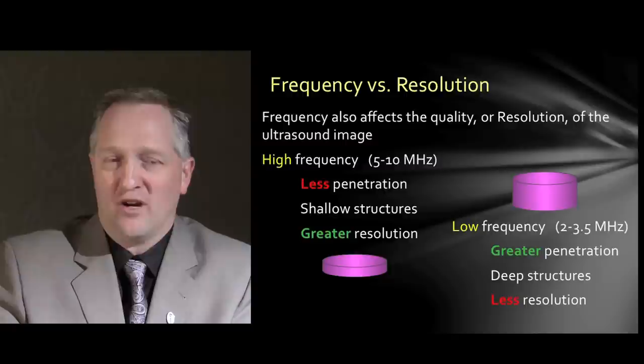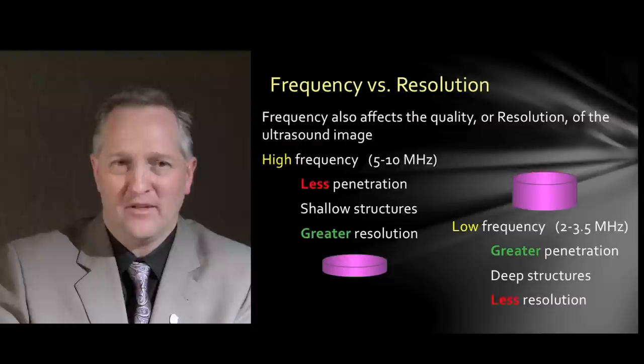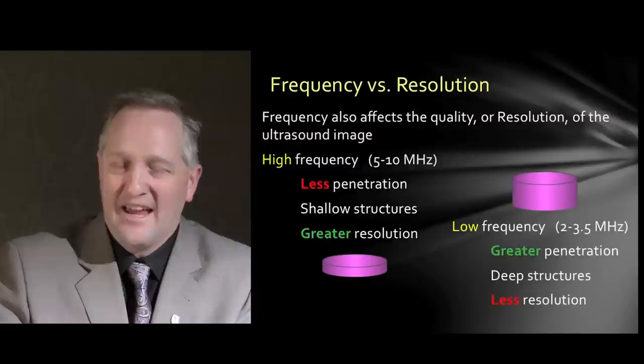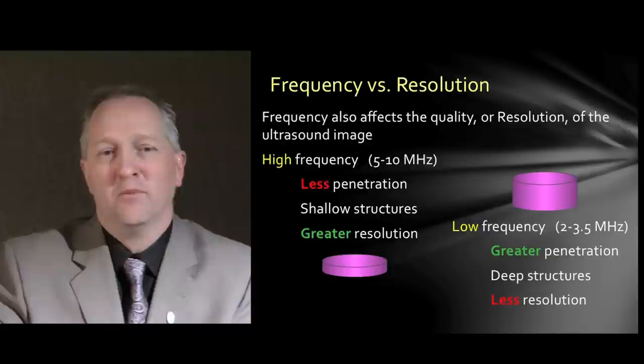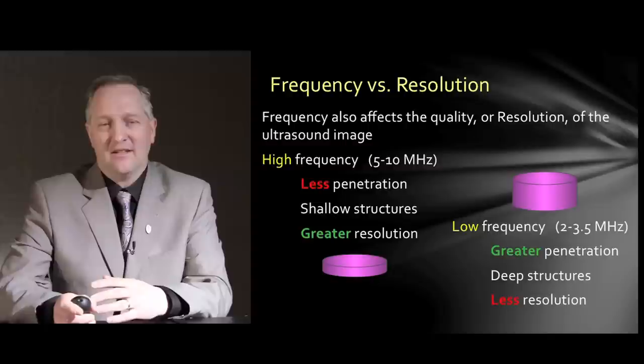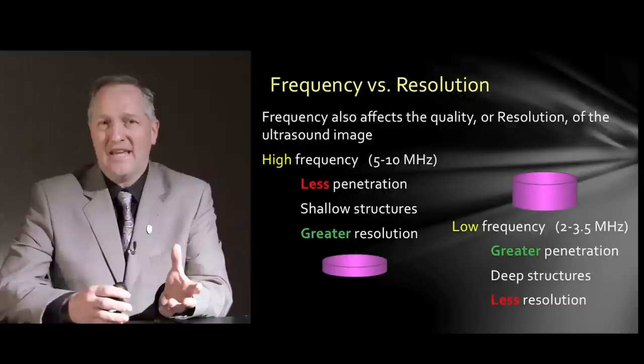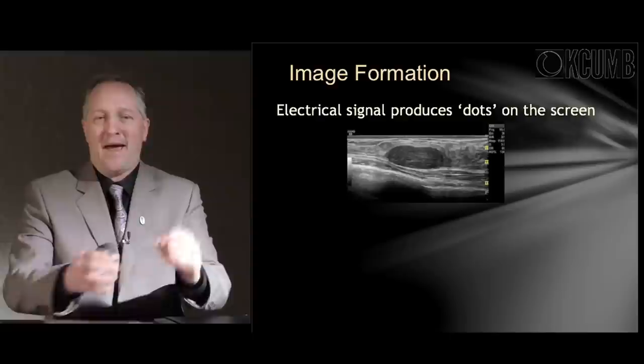The benefit of a high-frequency crystal is that since the echo returns faster, you get better resolution on screen. Conversely, a low-frequency thicker crystal vibrates at a lower cycle and goes deeper into tissue because the wavelength is spread out, giving it greater penetrating ability. Low-frequency ultrasound allows you to image deep structures, but there are tradeoffs — you get less of the echo back, resulting in less resolution with the lower frequency vibration.